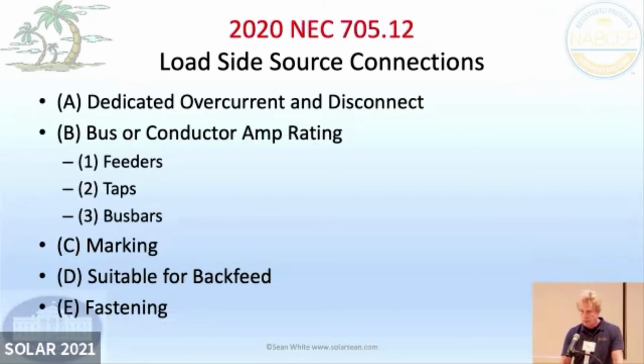And so this is not between the meter and the main breaker on your house. This would be between the main breaker, or main service disconnect, and the load side of it. So loads are all the light bulbs and all the things that go there. We call it, this is Section 705.12.